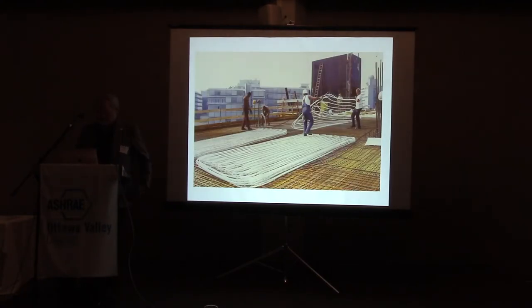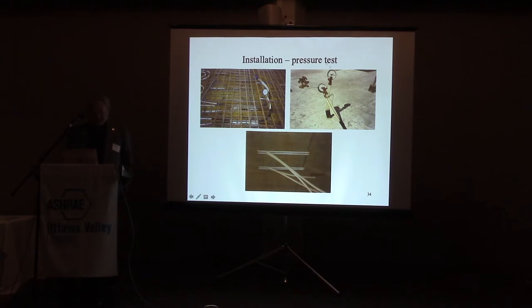But very often, of course, you have to do a pressure test. So when you have installed the piping between the reinforcement, you do a pressure test to make sure everything is tight. And also after you have poured the concrete, you do a pressure test. That's very important. After that, the pipes are really protected and nothing can happen. Until somebody was so stupid that they did a pressure test in winter and forgot to take out the water, and the pipes were destroyed. The structure was fortunately not destroyed. And the manufacturer of the pipe was happy, now they sold another system again. But there was a long discussion about who was responsible.